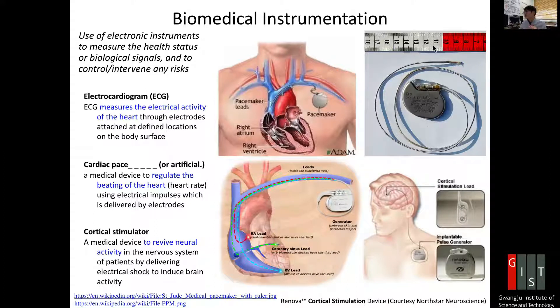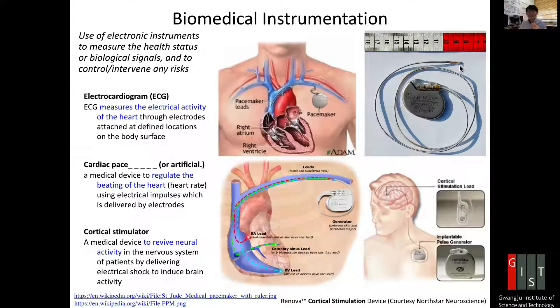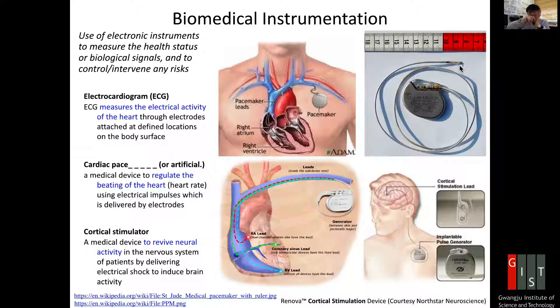The pacemaker is about this small size — it's not very big. It contains a large battery which sends out electrical impulses through the electrode. At the tip of the electrode, there is a wire with a helix so that you actually insert it into the heart by rotating and then fixing it. This pacemaker lead goes through the wall of the vein, which is connected directly to the heart.